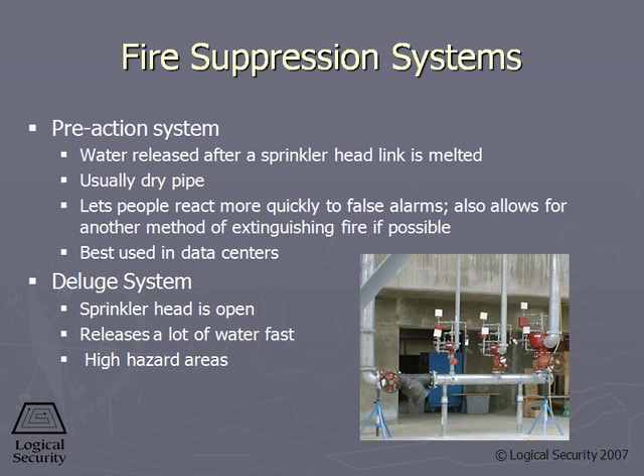The fourth and final sprinkler system you need to understand is called the deluge system. The deluge system is where the sprinkler head is already wide open. There's a large volume of water located somewhere in the facility. Generally, it's high, like on the roof of the building. And when the alarm sounds, the valve opens, floods all the pipes, all the sprinkler heads are already open. So this is very fast to react, very high volume of water, very high water damage. But at the same time, we would use the deluge systems where I have to ensure that I put the fire out as rapidly as possible. This is commonly used where we have a lot of flammable goods that if these flammable goods catch on fire, I may never get the fire put out until total destruction occurs.